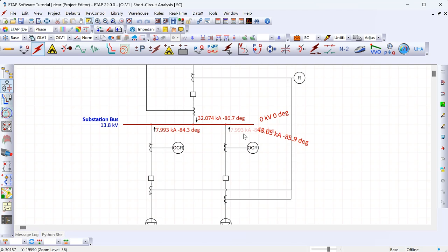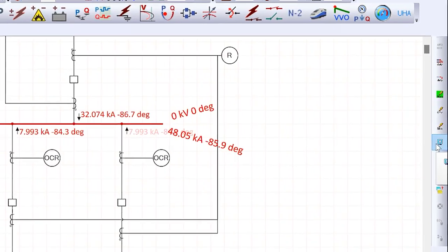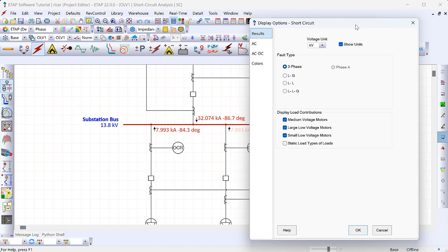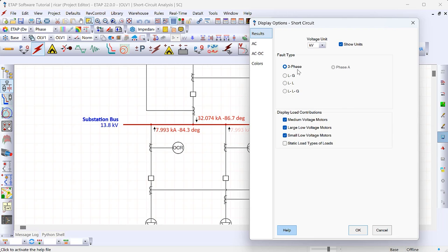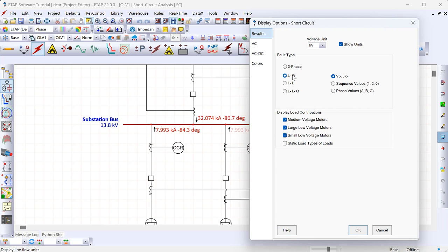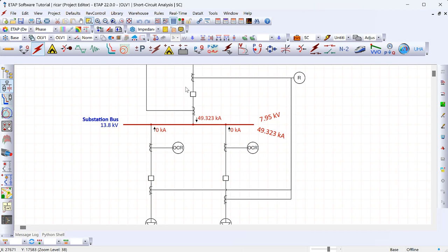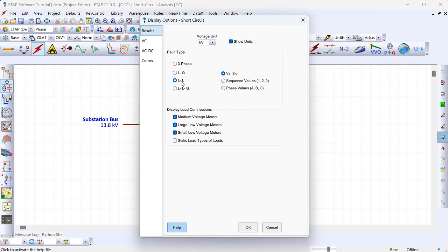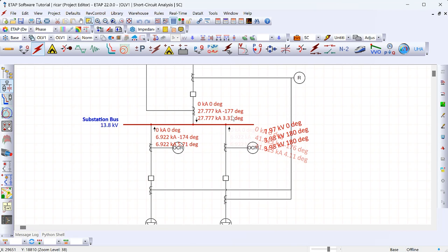The information currently displayed is for a three-phase fault. Clicking this icon brings up a window showing that ETAP runs all different fault types — three-phase, line-to-ground, line-to-line, and line-to-line-to-ground — and then you select what to display. You can switch the display to line-to-ground, and ETAP gives you the option to display 3I0, which is helpful for protection coordination, or the phase values. You can also change to line-to-line and select phase values instead of 3I0.